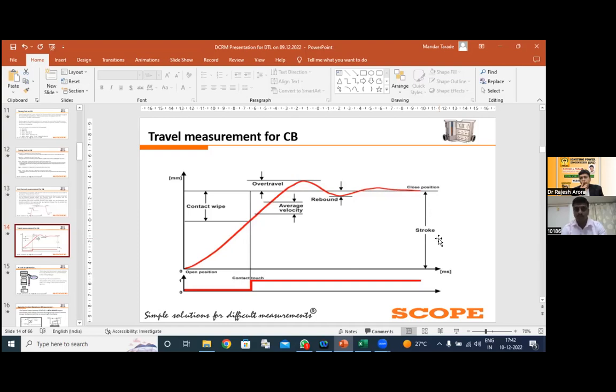So the parameters we get with the help of these travel traces are: first, the total travel; second, the contact travel; third, the contact wipe; fourth, the over travel; fifth, the rebound; sixth, the default velocity; and seventh, the datum velocity. Datum velocity is basically the average velocity, or the velocity between any 2 random points where we want to measure the velocity.